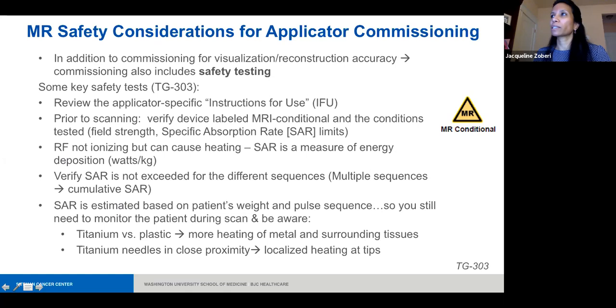You should see something like this, and verify the conditions under which it's tested—what's the field strength, what's the specific absorption rate. Keep in mind the RF in these MRI units is not ionizing, but it can cause heating, and SAR is a measure of that energy deposition which leads to heating. You really want to verify that SAR is not exceeded for the different sequences, and keep in mind multiple sequences mean that SAR is accumulating.